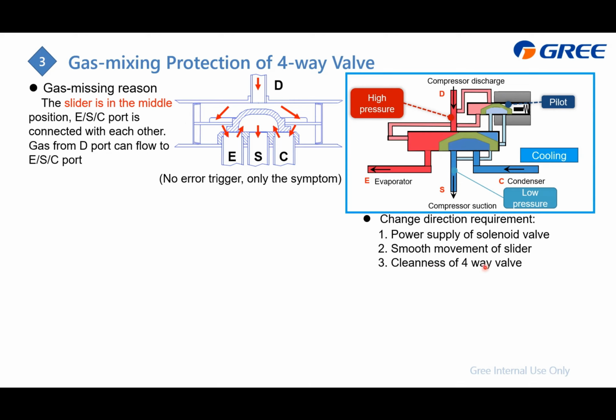The next is to ensure the cleanness of the four-way valve. For example, impurities which jam or block the capillary will also make the pilot valve unable to get the high or low pressure. If you cannot get the pressure, it cannot move this one. If it cannot move this one, this slider also cannot change direction successfully.